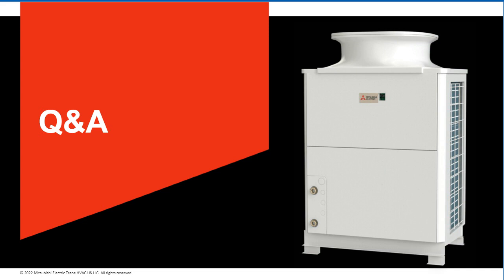So, I think one of the questions I saw as I was scrolling through is, from a standby state, how long to take it from 50 degrees to 170 or 150, whatever you have for your primary set point. It's going to do that in under a few minutes. So it's a very quick response time as far as getting up to that temperature from an off state or from a defrost state.